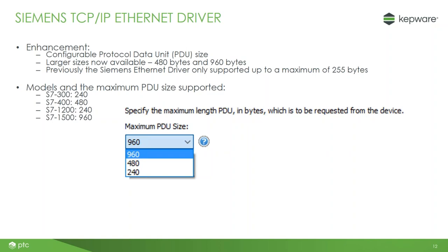For the more powerful 400s and 1500s, what could conceivably happen with the 255 limit is if I was trying to read or write significant volumes of data, typically at high rates - think tens of thousands of tags with sub 1 hertz update rates - I could be sending so much traffic over the wire that I could eventually start to lose updates. So what we've enabled in this release is the ability to select your maximum PDU size.